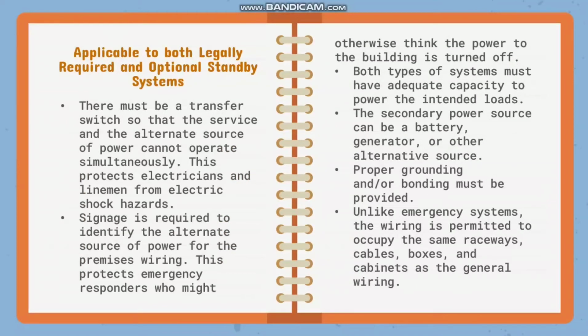So, applicable to both legally required and optional standby systems. First, there must be a transfer switch so that the service and alternate source of power cannot operate simultaneously. This protects electricians and linemen from electric shock hazards. Signage is required to identify the alternate source of power for the premises wiring. This protects emergency responders who might otherwise think the power to the building is turned off.